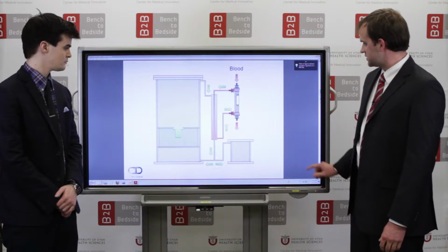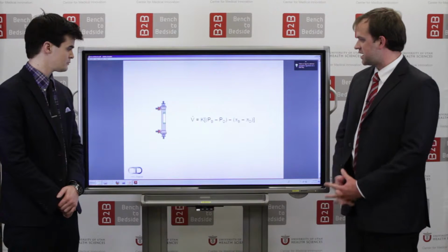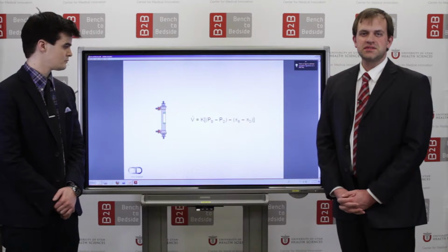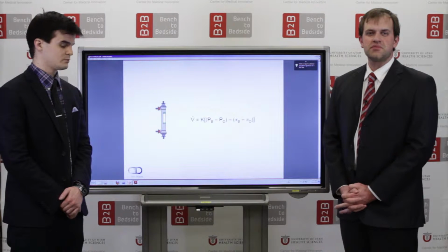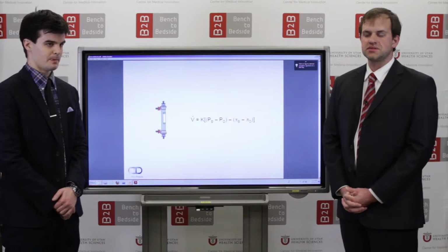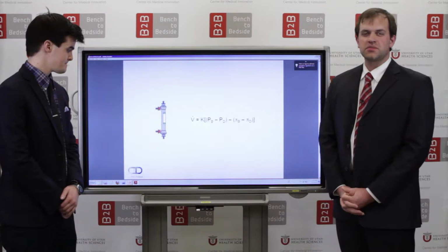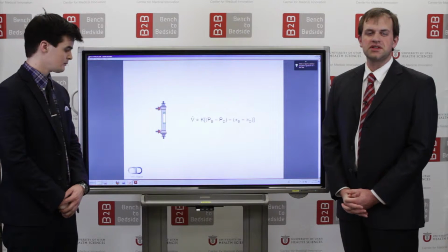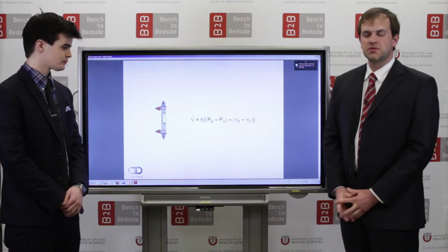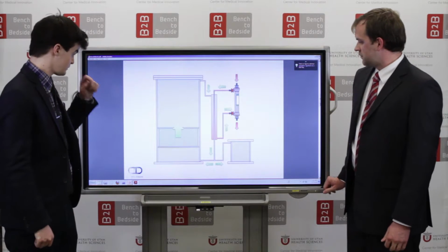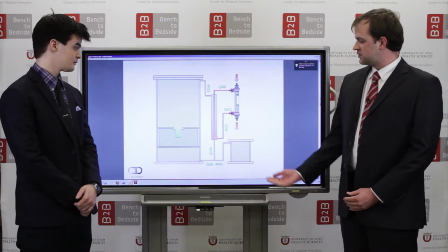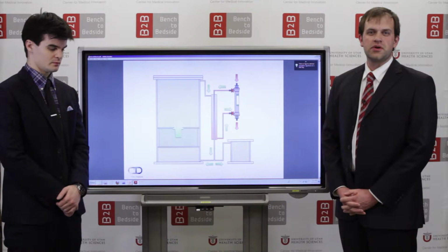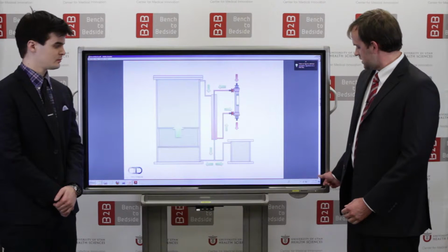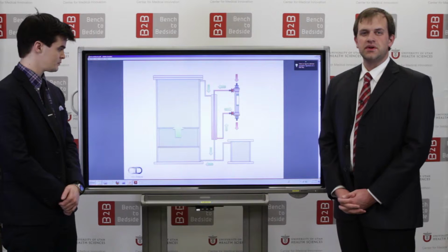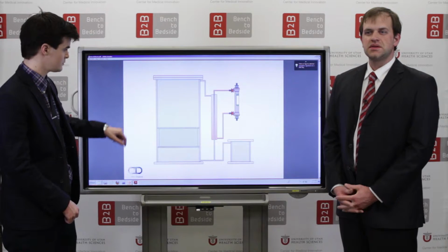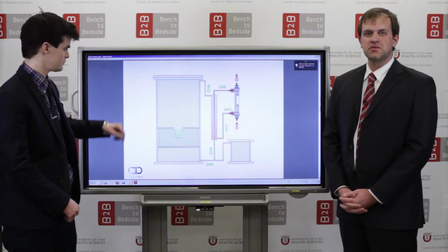In the dialysis cartridge here, blood flows in and dialysate flows in. Starling forces create a balance that can cause a net movement of fluid into or out of the patient's blood. By manipulating the osmotic pressure and the pressure of the dialysate, we can either remove fluid from a patient or add more fluid. Fluid will originally come into a fluid extractor to fill it up due to a low pressure in the dialysate.